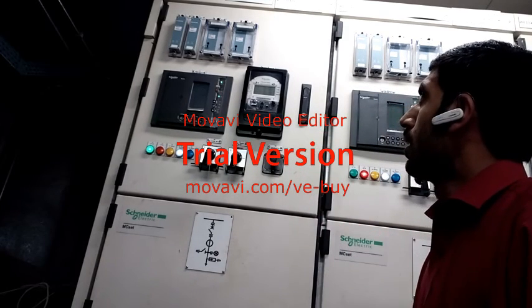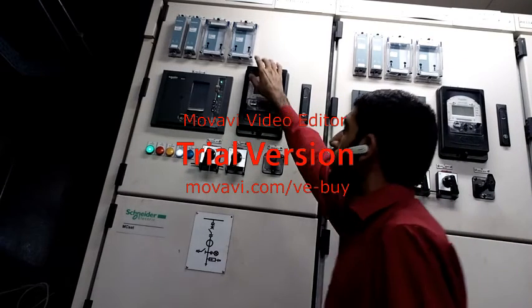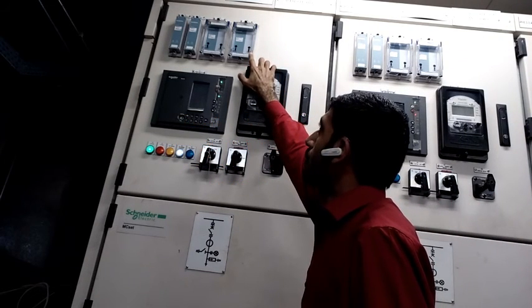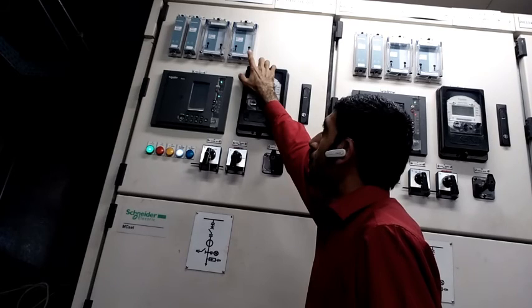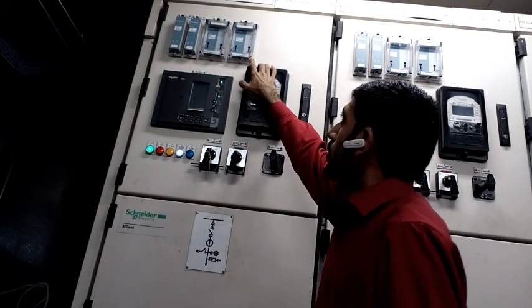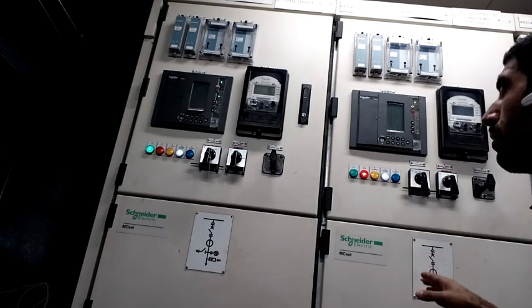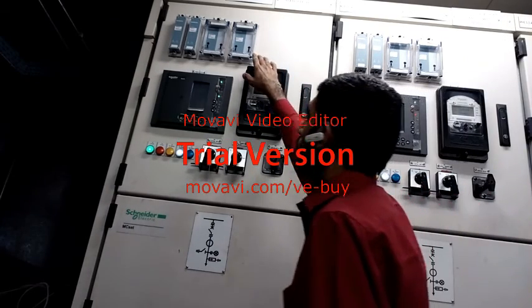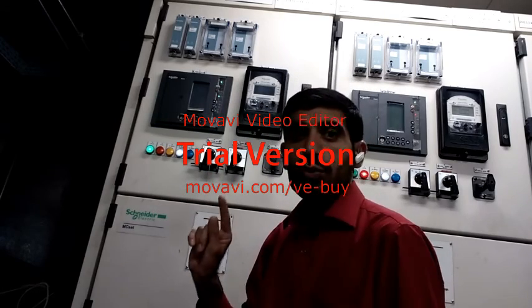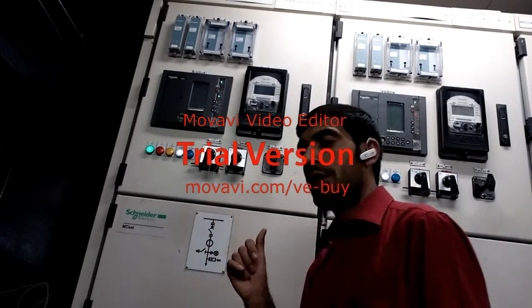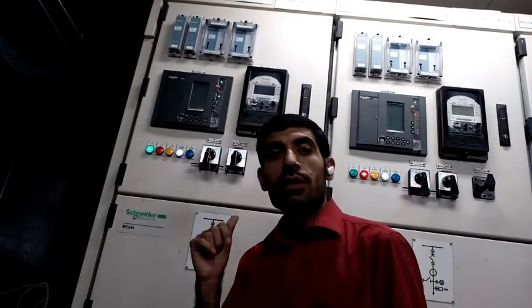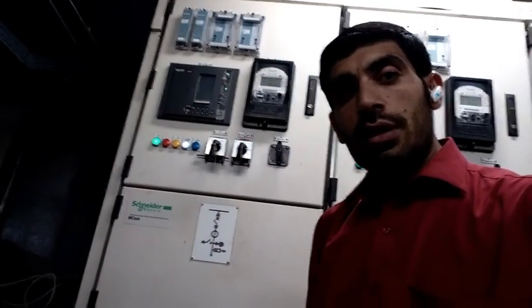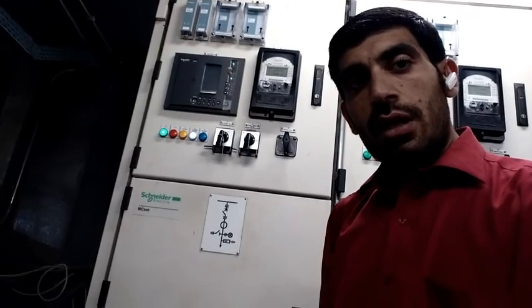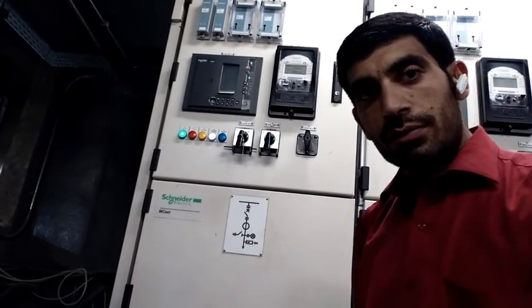In front of me I have this feeder. This feeder has different types of components. On the upper front I have an auxiliary relay, made by Siemens. This whole switchgear is made by Schneider. This relay has two DC coils. Each coil's rated voltage is 125 volt DC, and this relay has two coils.